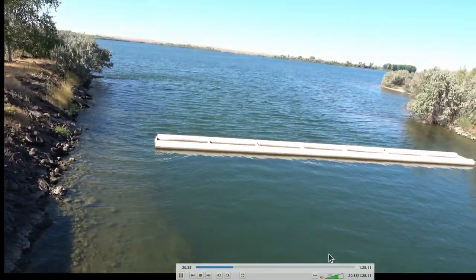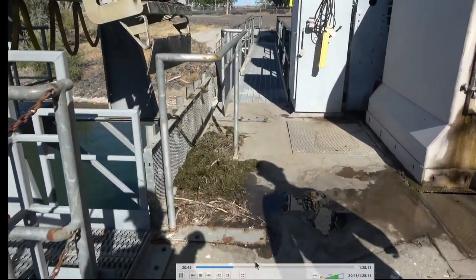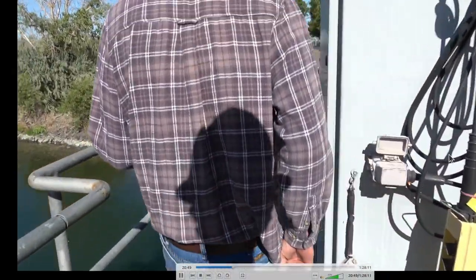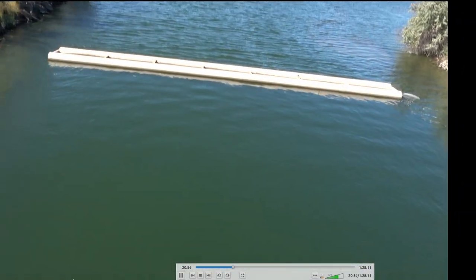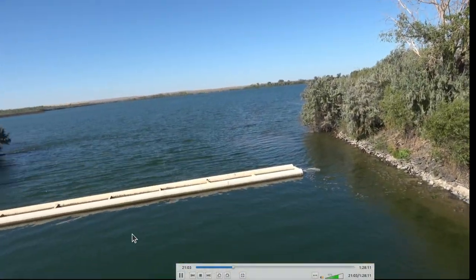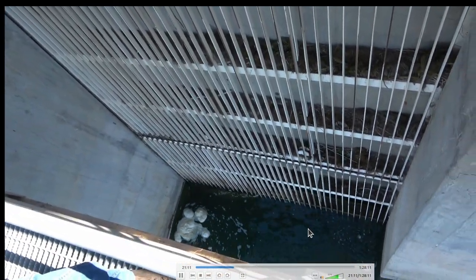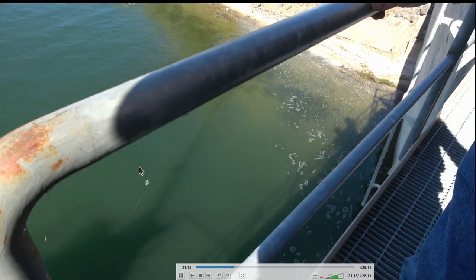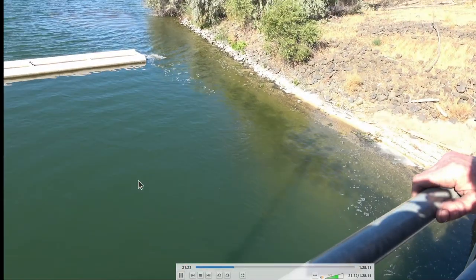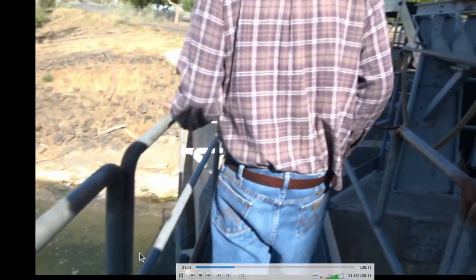There's a wave breaker here that seems to help knocking down waves in high winds. These are the traveling screens — they filter out any debris. This is stuff that got pulled up off the trash rack out front. Certain times of the year you get a lot of debris blowing in, and it can be a disaster if these screens get too much buildup — they won't roll. The high differential pressure pins the screen against the frame, so if the DP gets too high, it will run the screen.